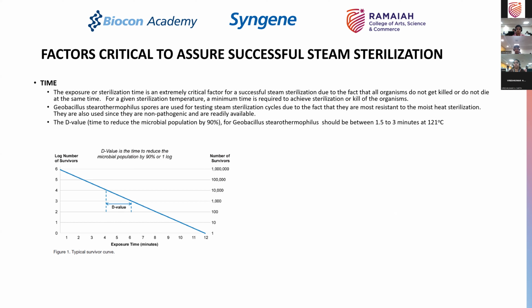You know how many spores were there before you put them in, and then after the sterilization cycle you test them to make sure that none of them are surviving, because those strips are chosen so that you have a 10 to the power of 6 kill rate or higher. So that's a technique which is used for measuring the success of steam sterilization.